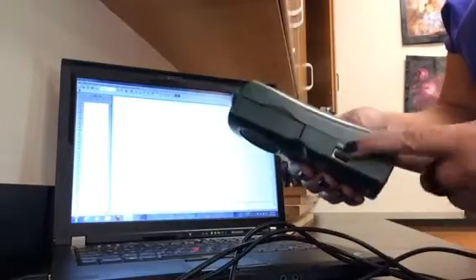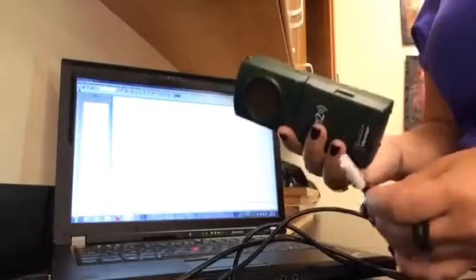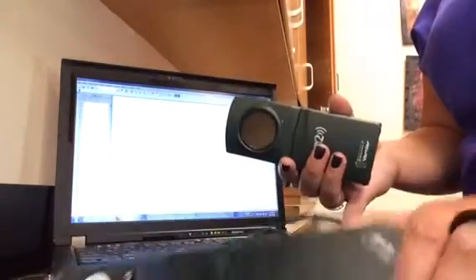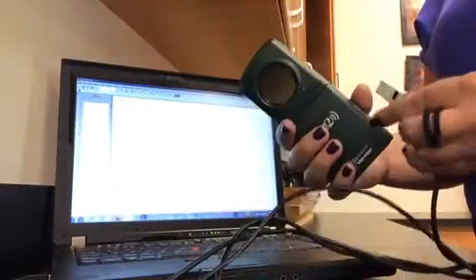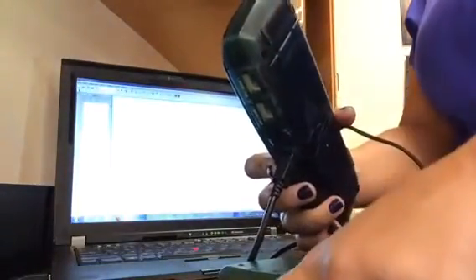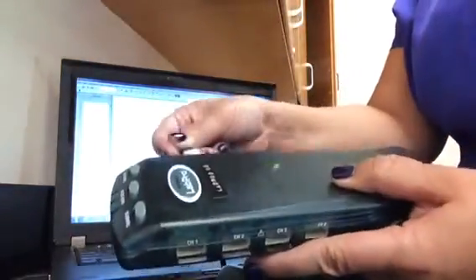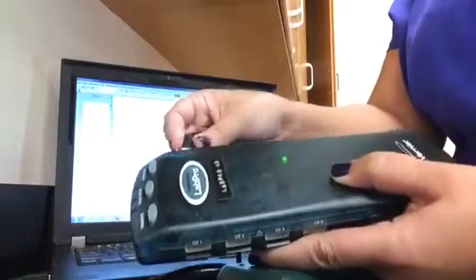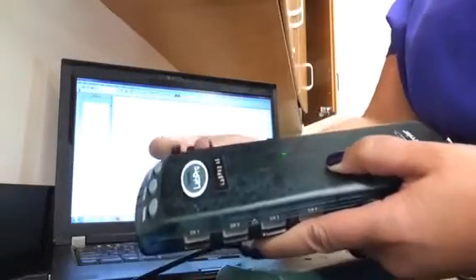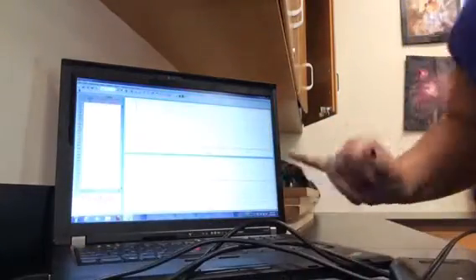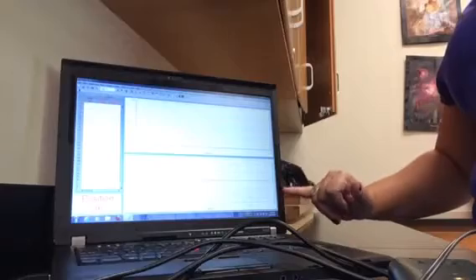So simply, there's only one thing to do with this, just to plug it in. So we'll take one side, and these cables should be in the container with the sensor. So the sensor should have, whatever kind of sensor you're using, should have cables that will hook from here up to your LabPro. And they only fit one of these inputs. On the LabPro, you'll see there's a bunch of channels here, and then on this side, you've got a couple other inputs. Well, your cable will only fit in one type of input, so you never have to worry about plugging it into the wrong thing. And so you plug it in over here, and once I do that, immediately what will happen is the computer will adjust, and you can see that quick, it has adjusted to the type of sensor that I have.